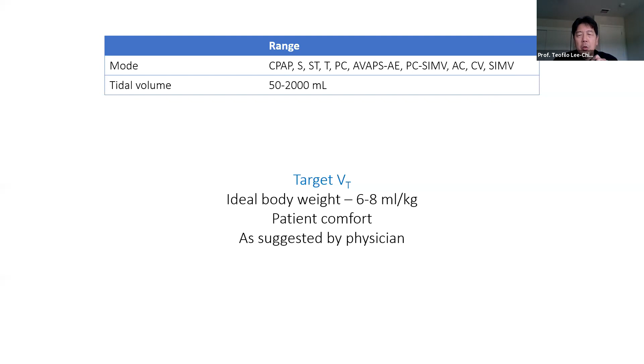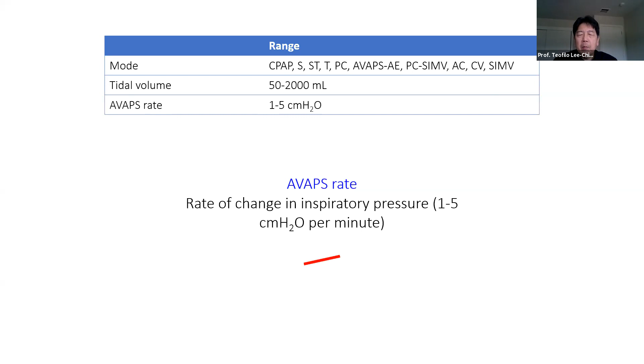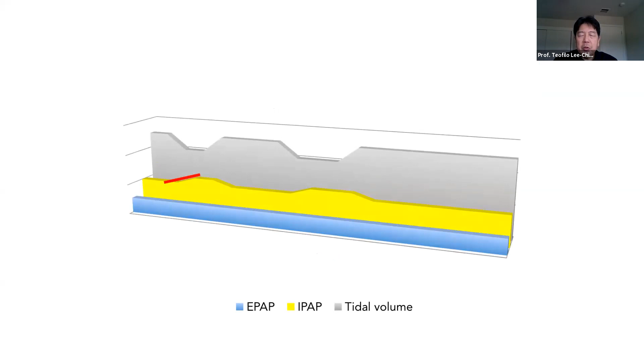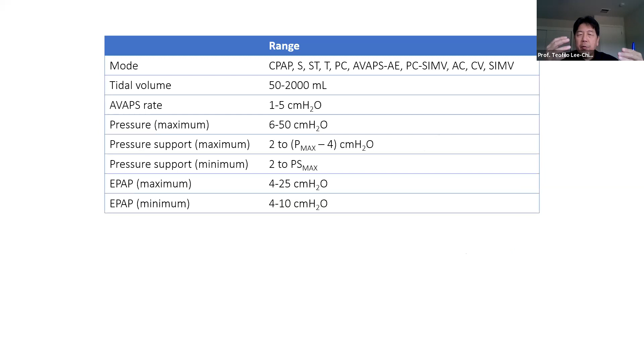The AVAPS rate has been discussed earlier. It is nothing more than a change in your inspiratory pressure. And for most of our patients, I would suggest that you put a default setting of 5 cm water per minute. So this is your AVAPS rate, how quickly it changes to reach your target tidal volume. Then you have your rates, you're all familiar with them.